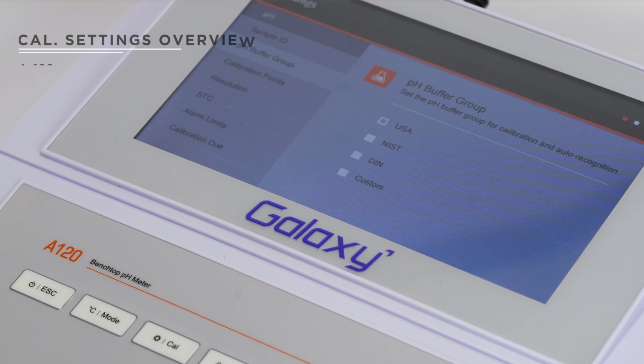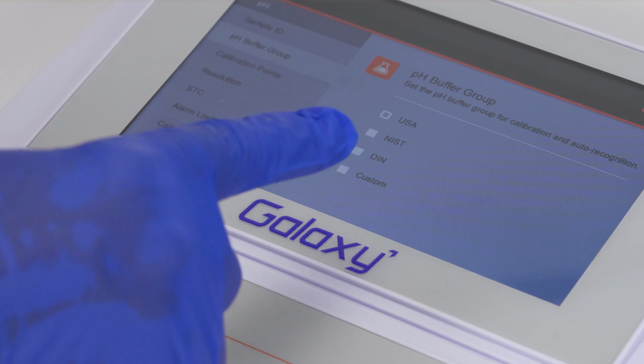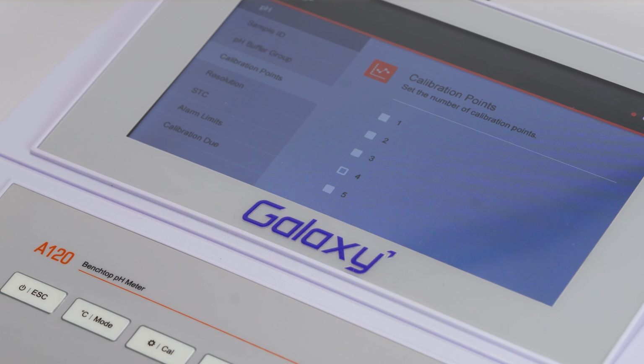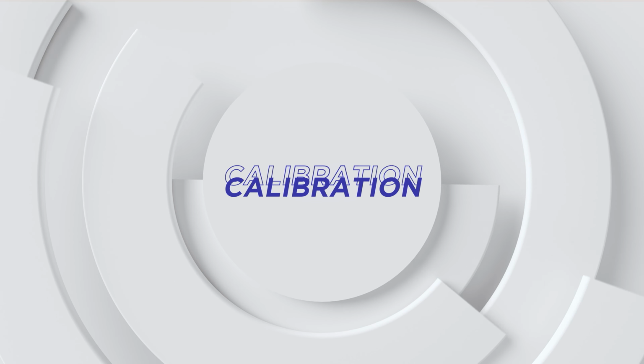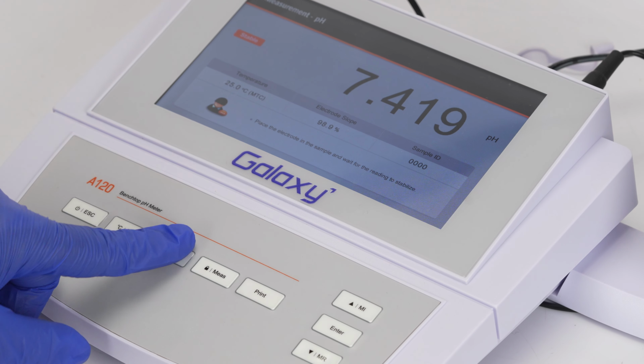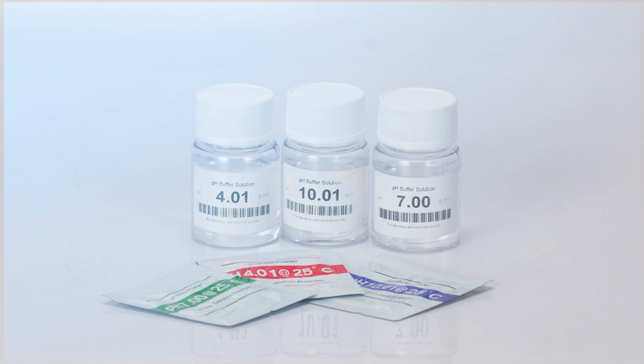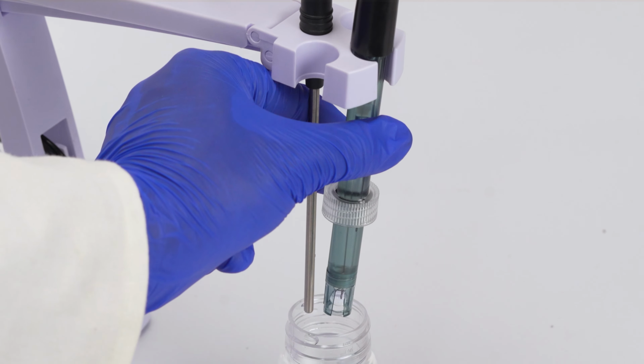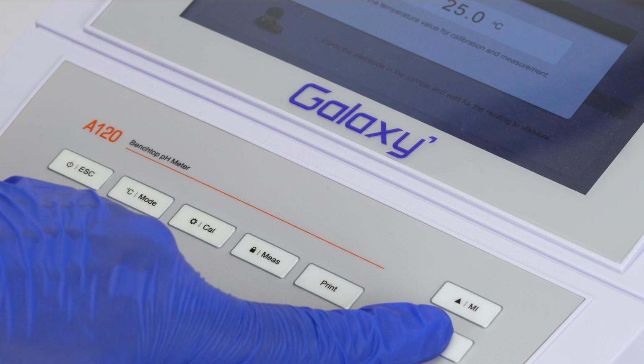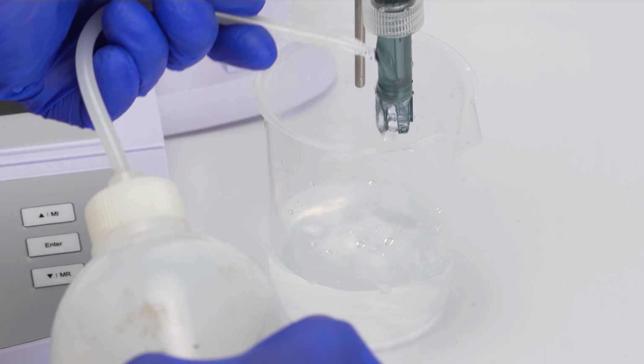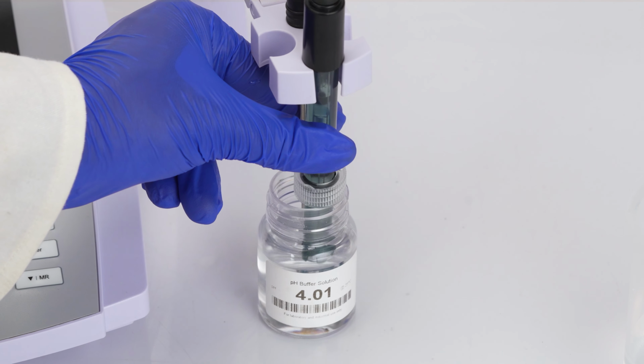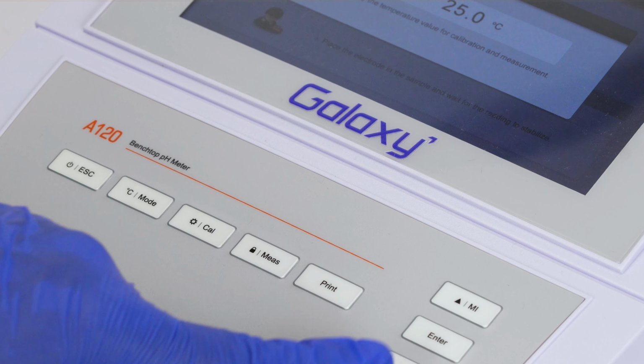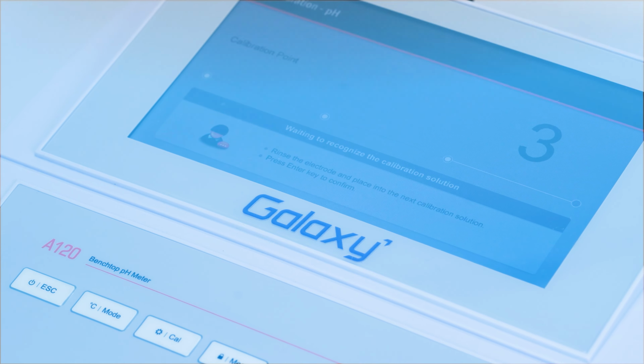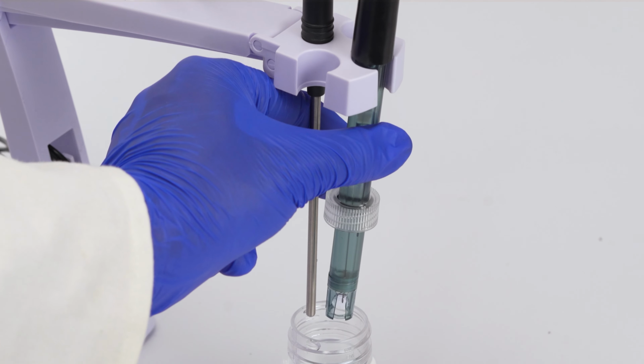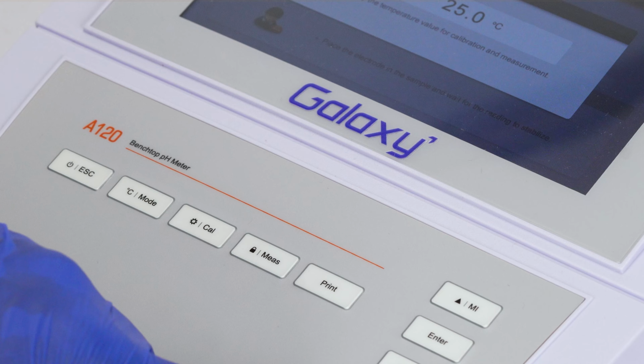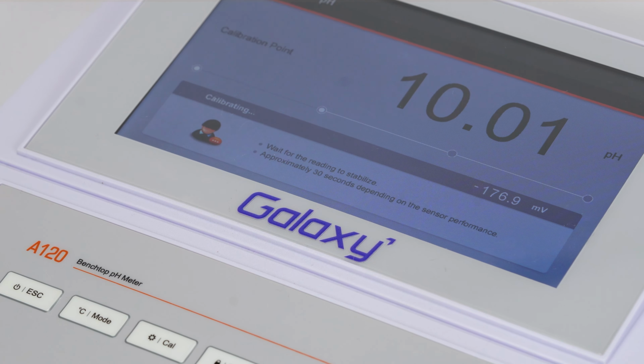You can select your preferred pH buffer group, USA, NIST, DIN, or custom values, and set the number of calibration points from 1 to 5 depending on your requirements. Press the Cal key to start calibration with 3 standard buffer solutions. Rinse the electrode, immerse it in the first buffer, and press enter. When Cal 2 displays, rinse the electrode, immerse it in the second buffer, pH 4.01, and press enter. For Cal 3, rinse the electrode, immerse the electrode in the third buffer, pH 10.01, and press enter again. The display will confirm calibration complete.